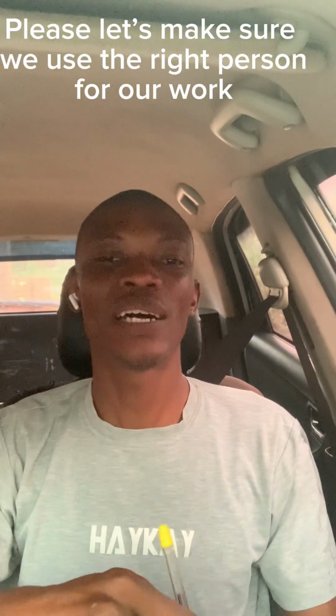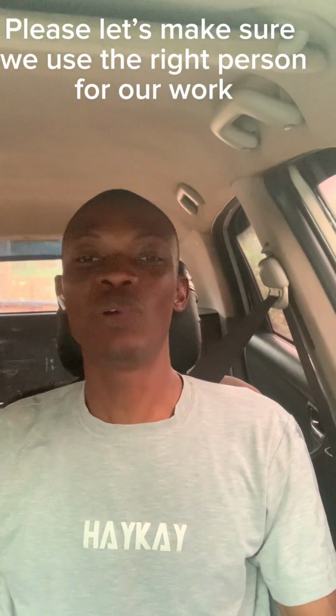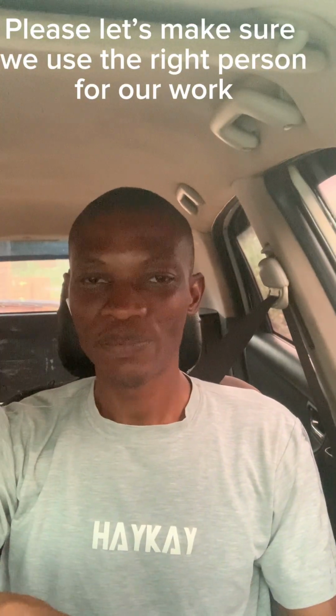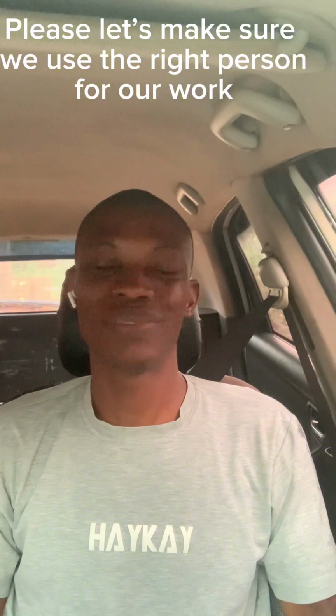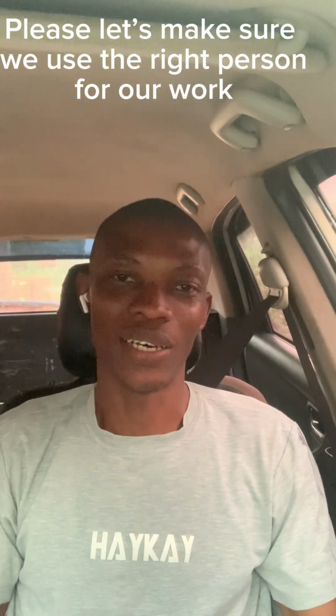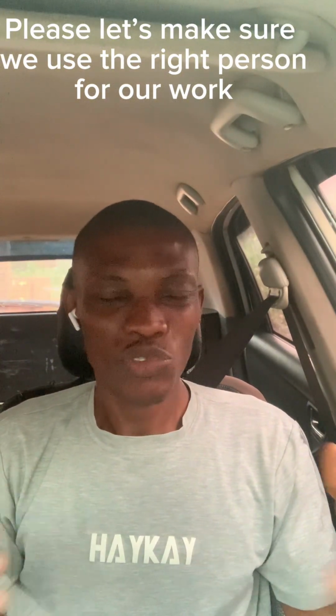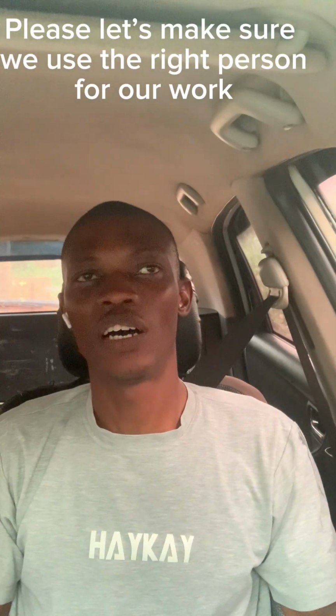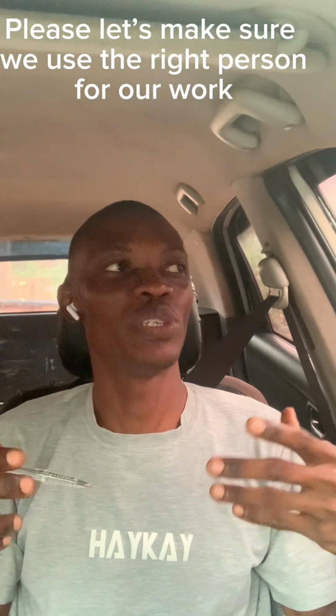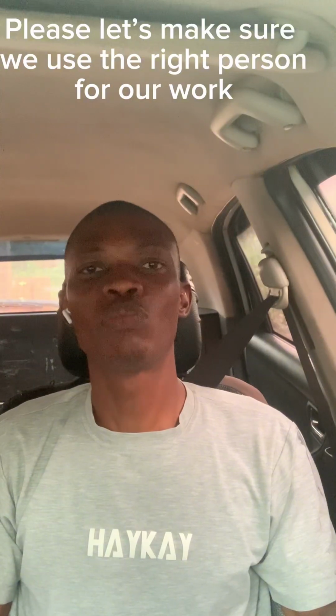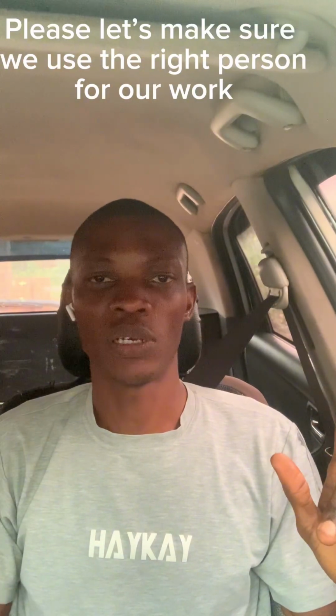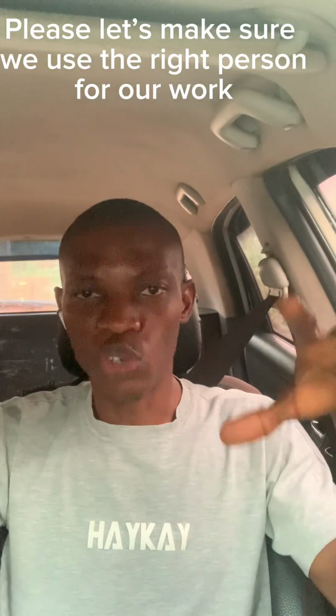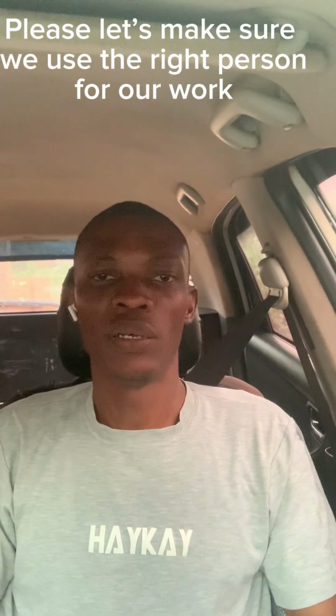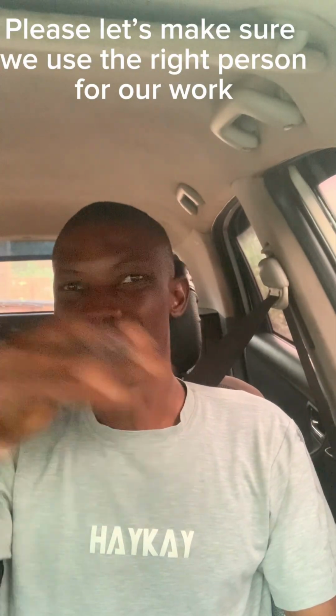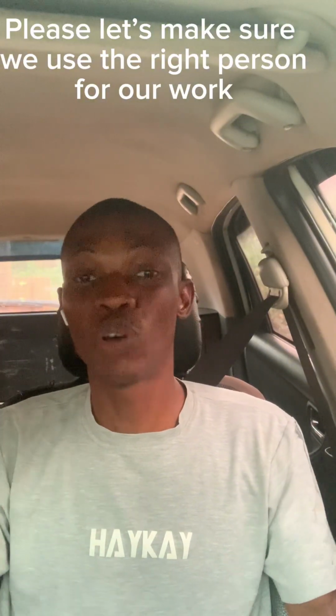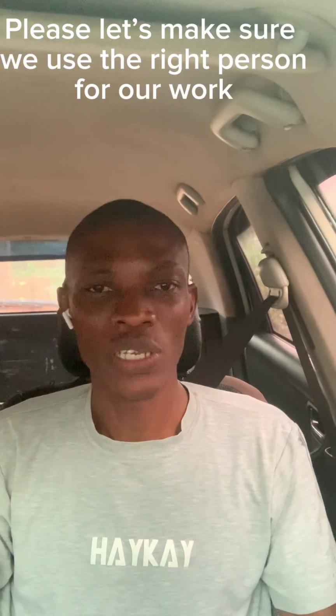So you coming here now to say that because the transformer is far away from the house, that is why we have low voltage as well - to me, probably, what I observe used to be the cause is when you have too much load on a particular transformer, there'll be a drop in voltage, a drop in power. It's not about distance, no. It's when you have too much load, more than what the transformer itself can handle, that's when we have such issues.